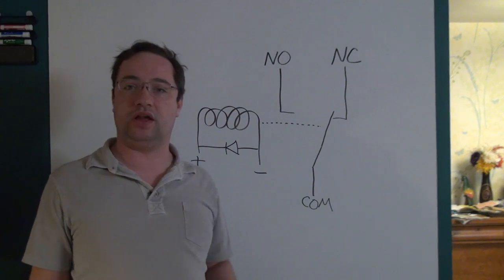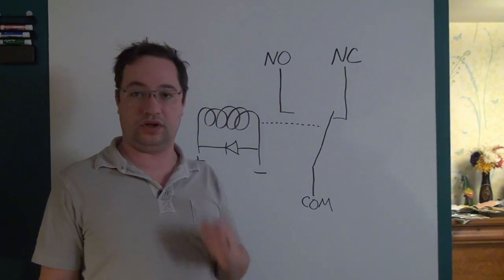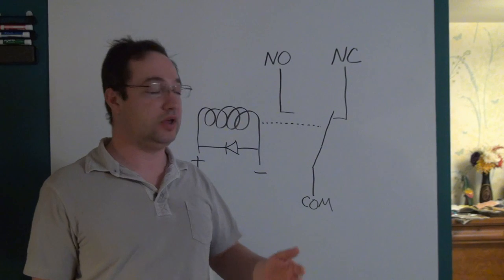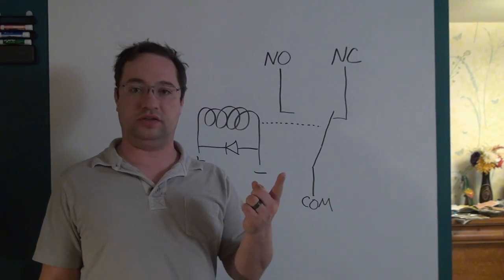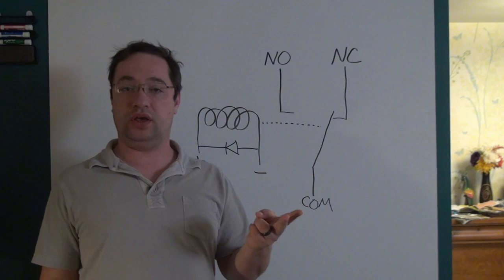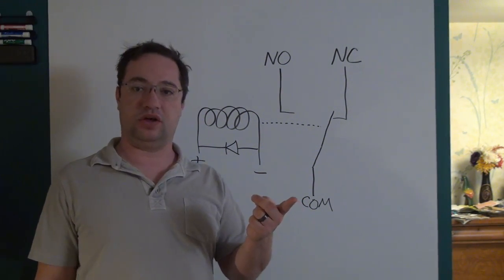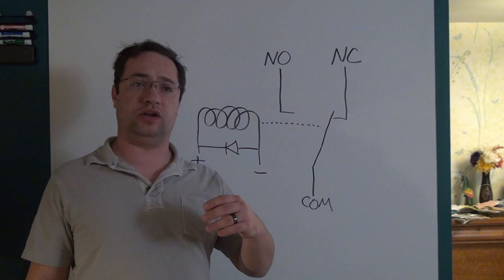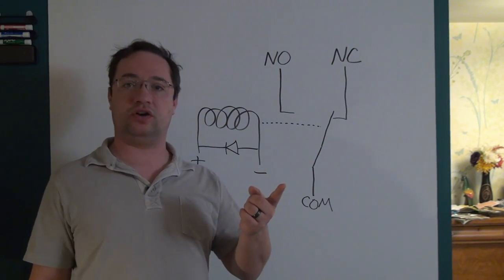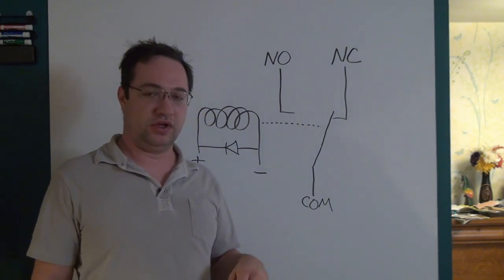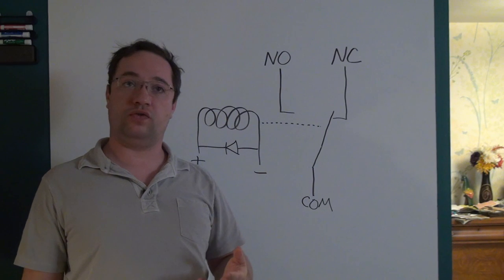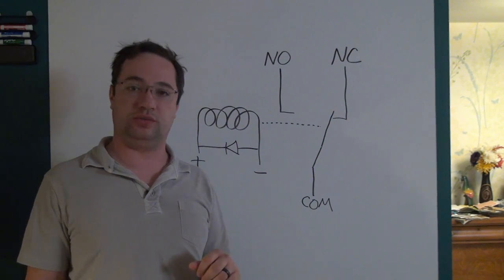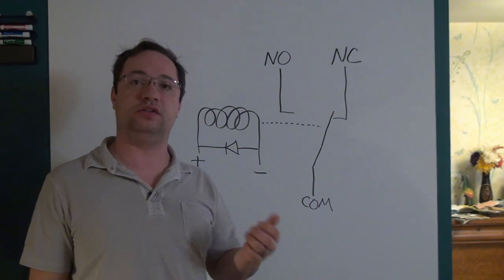The current rating is incredibly confusing. The rating can be given in AC, DC, or both, and not all relays can do AC and DC at the same time. There are also max currents and breaking currents. The profile of how the relay deals with current changes depending on whether it's designed for AC, DC, or both.